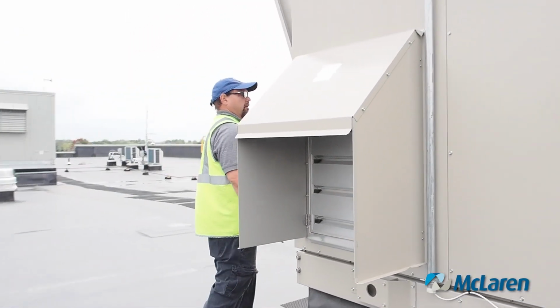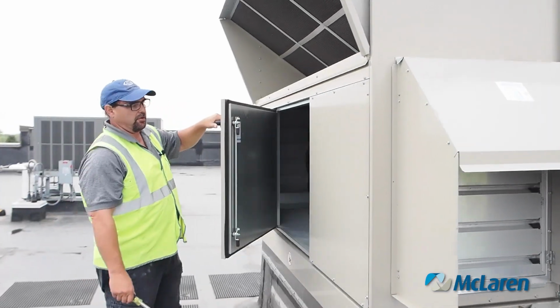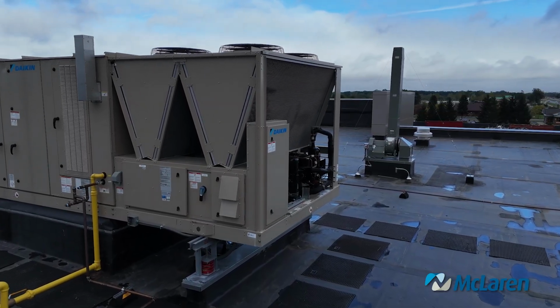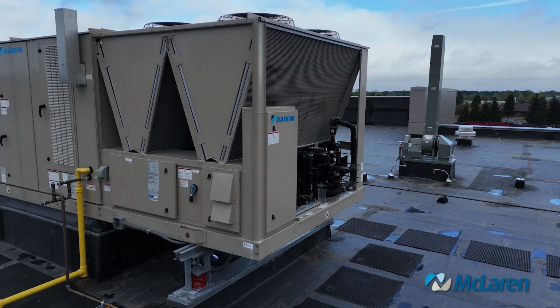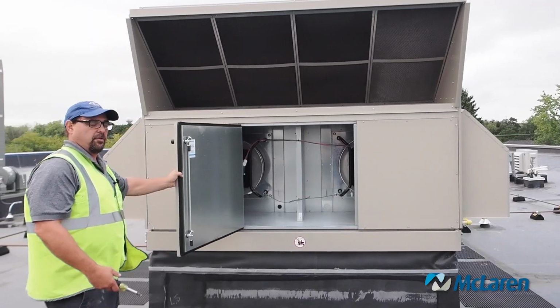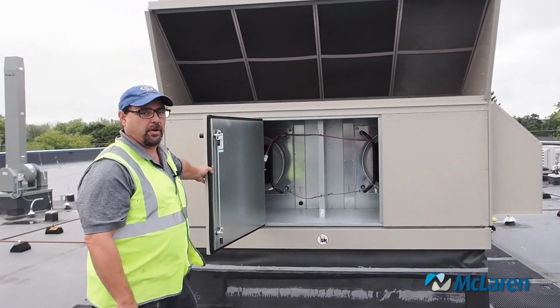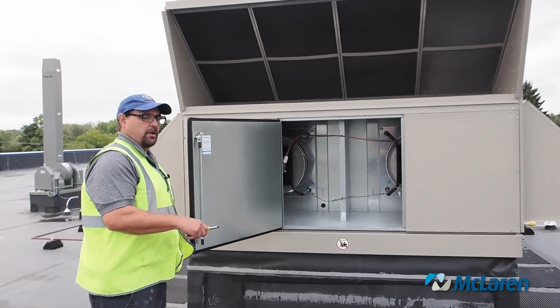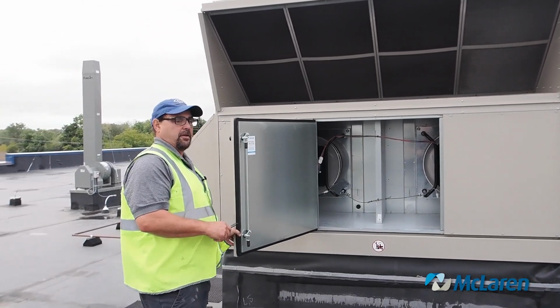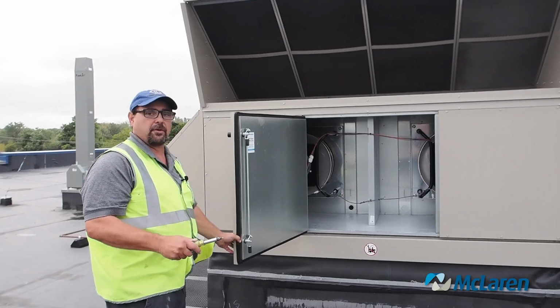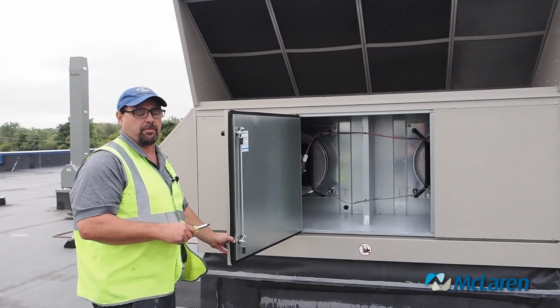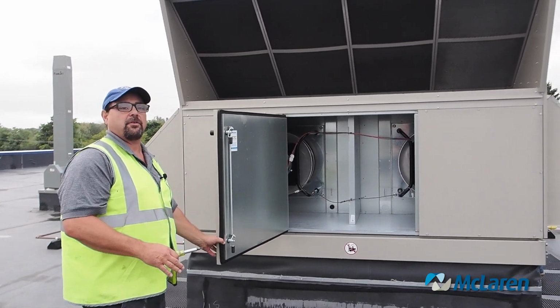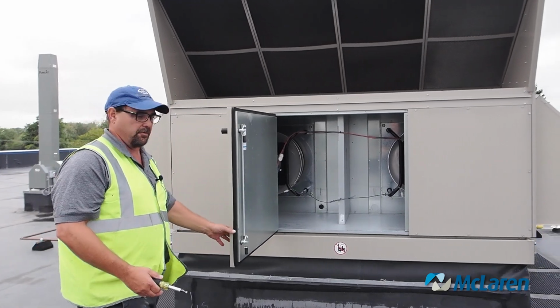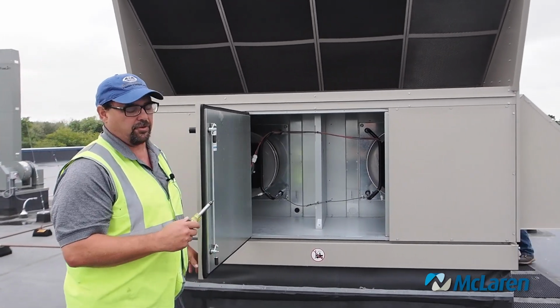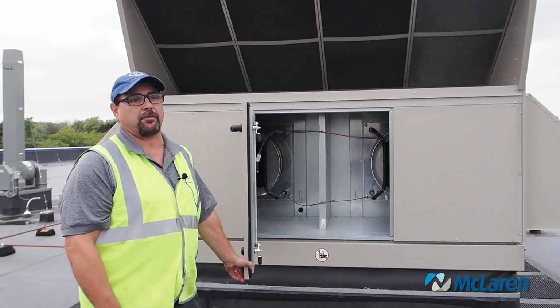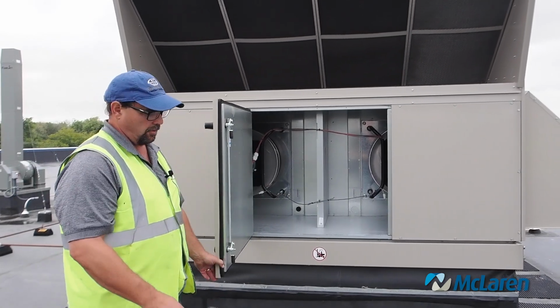Over on this side is access to your return fan section or exhaust fan section. Daikin calls them both. Just like the supply fan ECM motors, no maintenance. If one fails though, you replace it. It's not as critical on this to block off the fan. Let me rephrase that. This building might be as critical, so if you do have to get a fan, you should probably block it off as well. I'm not sure of the static considerations regarding this part of it. But it is, and I've seen those unfortunately thrown out as well, so something might have to be made. No maintenance though on these.